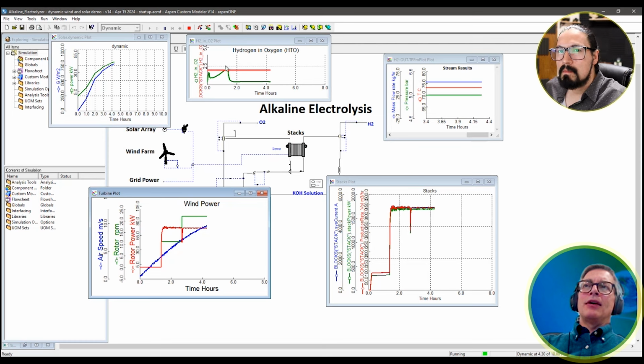So you can see now, over time, as I've increased the current density going to the stack, my hydrogen in oxygen has dropped down to very low levels. That's more of the typical operating condition that you see there.